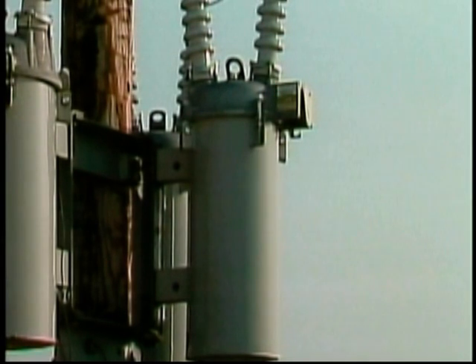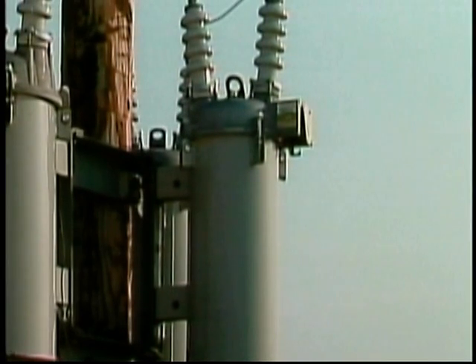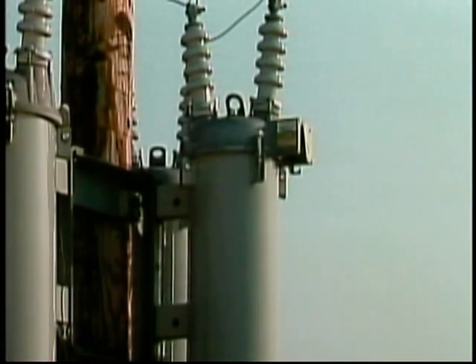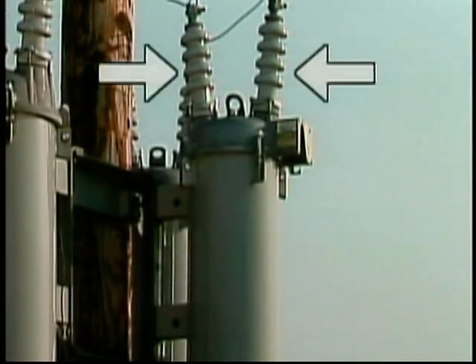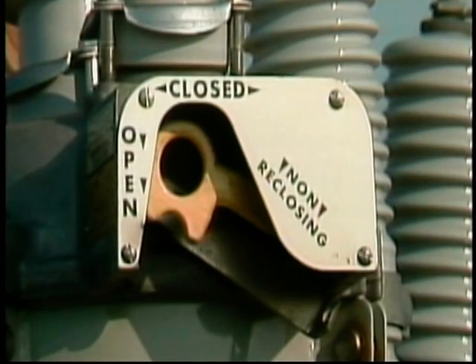One of these protective devices is a recloser. A recloser is a switch that automatically opens and recloses a circuit when a fault occurs on that circuit. A single-phase recloser has a cylindrical tank, like a distribution transformer and a distribution voltage regulator. However, it has two primary bushings and no secondary bushings. It also has an operating handle so that it may be opened or closed manually, for example, to isolate a portion of line for maintenance.